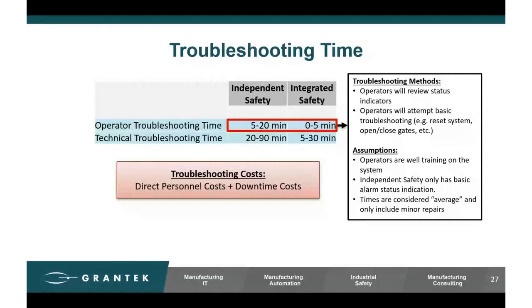Whereas an integrated safety system has all the diagnostic information built right in, telling you the status of everything going on. This info can easily be displayed right on an HMI—for example, there's a short between the two wires on interlock 5. If a fault code is displayed this way, troubleshooting time by the operator can, in theory, be reduced to zero, meaning the time to identify the issue. They know they need to call in maintenance; they're not going to fix it themselves. That's opposed to spending maybe 20 minutes just to figure out that they don't know what's wrong and still have to call maintenance anyway.